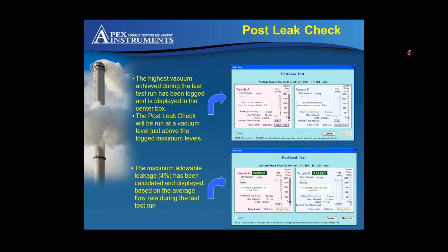Pass criteria is 4% of what your average sample rate was. The pre-leak is based on whatever you started your test at, while the post-leak is based on the average sample flow for the entire test, so it could be higher or lower. To pass, you have to be within 4% of that number.